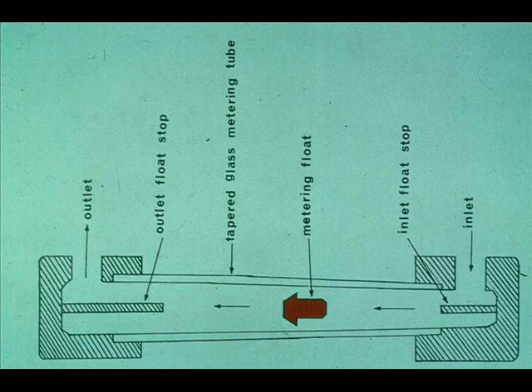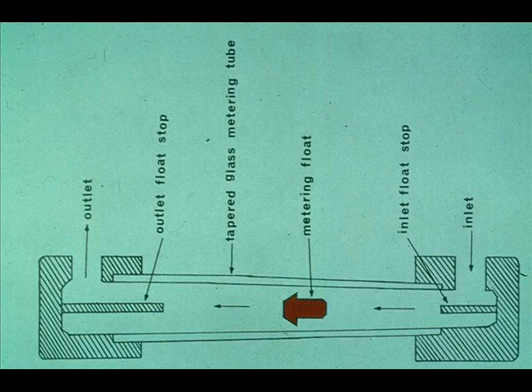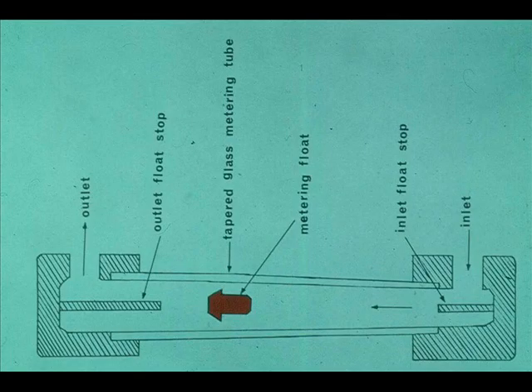The rotameter is another device for measuring flow. One type is a tapered glass or metal tube with a heavy float inside. The rotameter works on the principle of a constant pressure drop being maintained across the float by varying the annular open area between the float and the tube wall. An increase in flow rate causes the float to rise, increasing the annular area to compensate. The position of the float is used to determine the flow rate; you multiply the indicated float position by the provided meter constant.